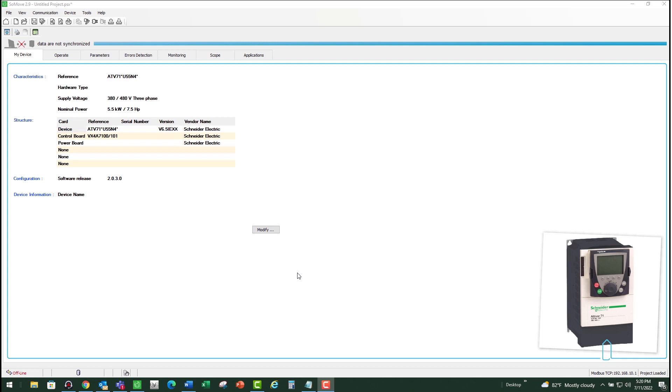In this video we are going to discuss OBF fault on ATV61 and ATV71 drives. The VFD monitors the voltage on the DC bus and when that DC bus reaches a trip threshold, the VFD trips on OBF fault.